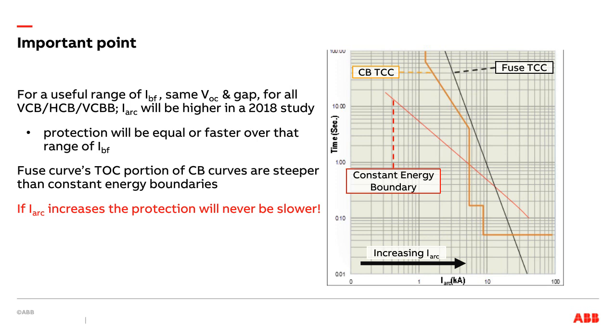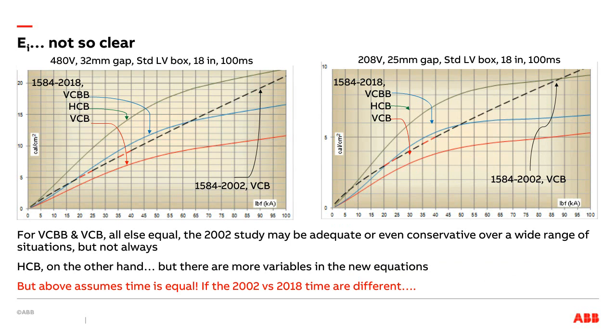What does that mean? That means that if you only know one thing about the 2018 study versus the 2002 study, and that is that the arcing current is higher, then what you do know is that your protection is going to be faster, or if your protection hits these horizontal portions in the circuit breaker, it's going to be the same speed. What you do know is that it will never be slower. Your protection is going to be the same or faster every single time per the studies when you compare the 2002 versus the 2018. So without looking at the time current curve, without knowing what the exact arcing current value is, you know your protection is going to clear at the same time or faster, never slower. And that's an important little fact we're going to use. When you look at incident energy, the comparisons are not quite so clear.